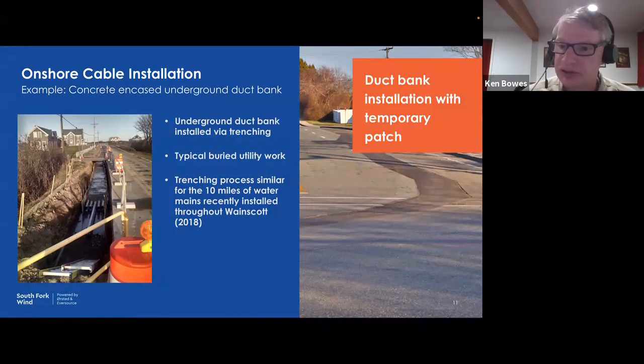Those are done in this concrete-encased conduit system. A trench is dug with a trench box, probably about 4 feet in width, and we'll dig inside of that, going down the path. We may have to do temporary shoring, using either plywood or lumber, because the soil conditions on Beach Lane are very sandy, so it's not a stable environment.